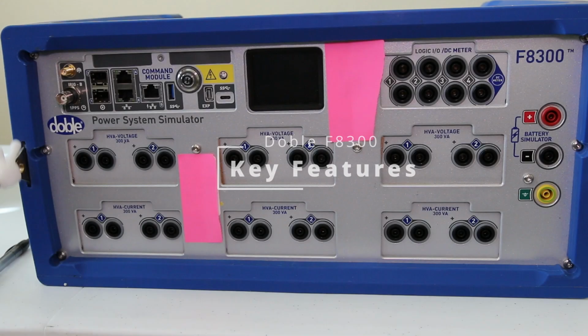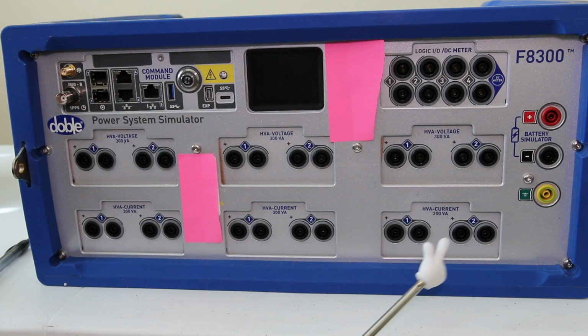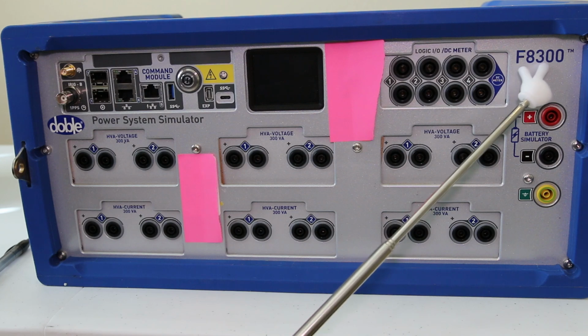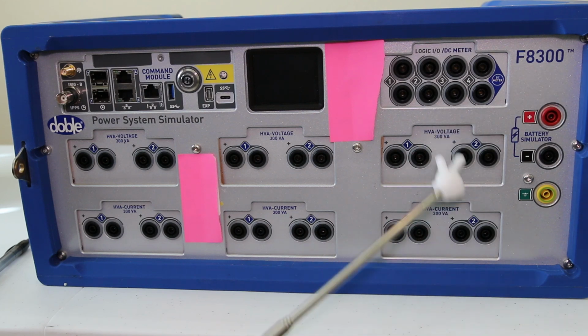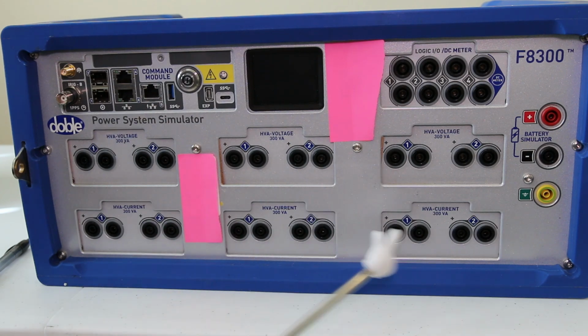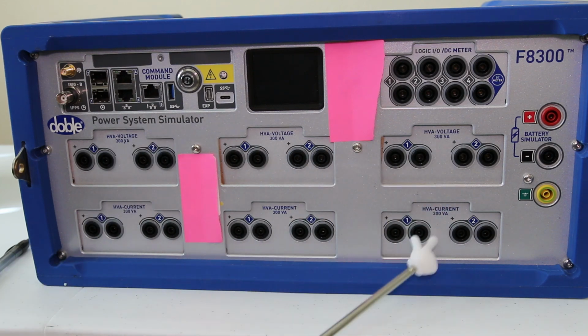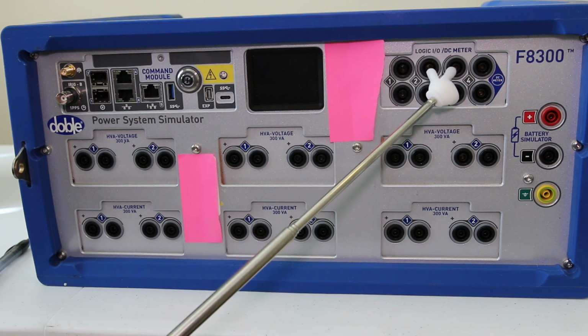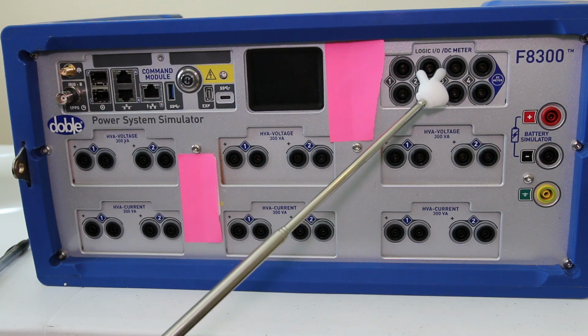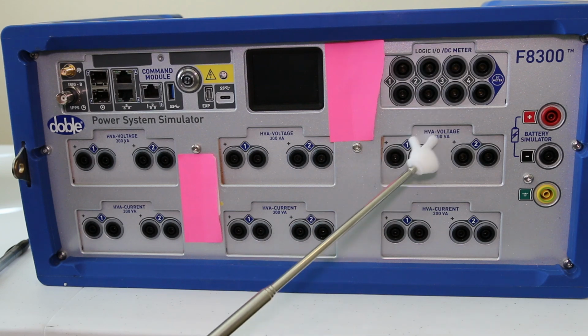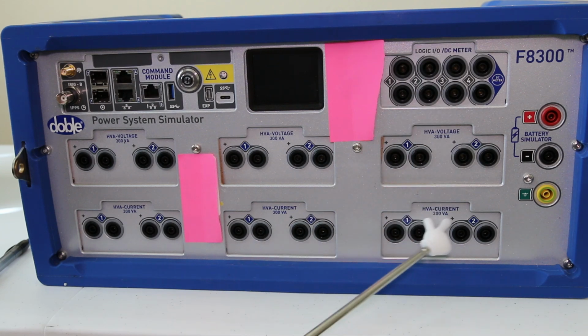The biggest thing with the Doble F8000 series, or this one in particular, the F8300, is that it has one slot up here and then six modular slots down here. Every single channel in here, every one of these little units, can be taken out and replaced with either another IO logic and transducer unit, one of the HVA voltage units, or one of the HVA current units. So you can have basically any combination.